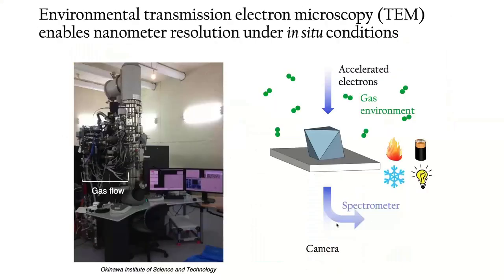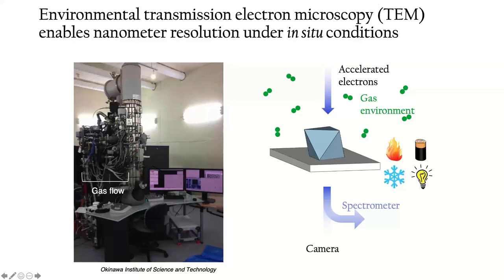All of these examples have to do with controlling light at the nanoscale and the atomic-resolution structural changes that occur, which brings me to the transmission electron microscope — the tool I'm going to use to describe most of the work I present today. At Stanford we use an environmental transmission electron microscope, a FEI (now Thermo Fisher) Titan. It has a gas delivery system off to the side that allows us to flow gas into the column, which is pumped away from the sample stage by a series of turbo pumps so we can keep a relatively low pressure of gas near the sample and look at samples in a dynamic environment.